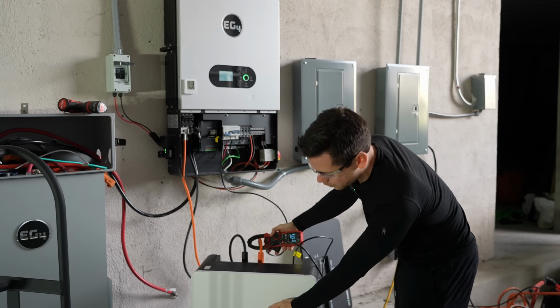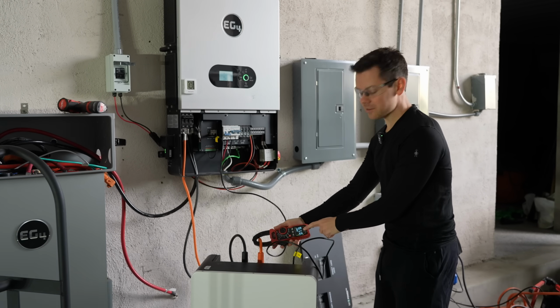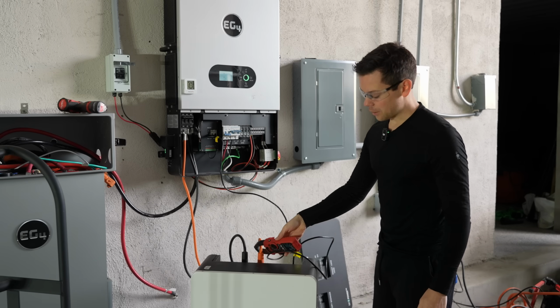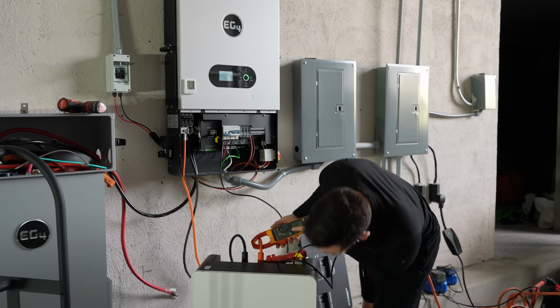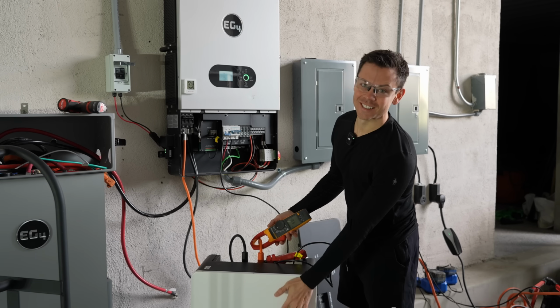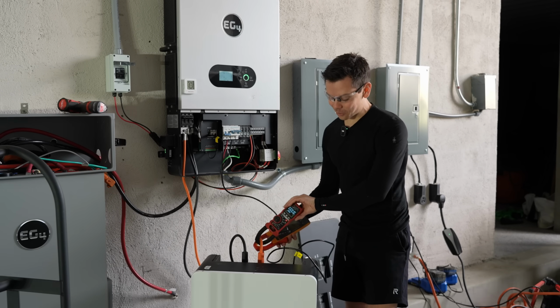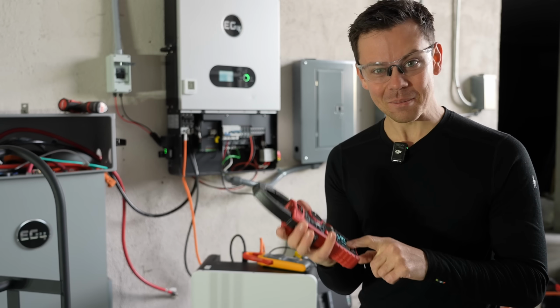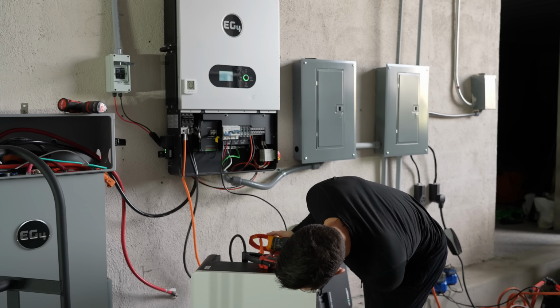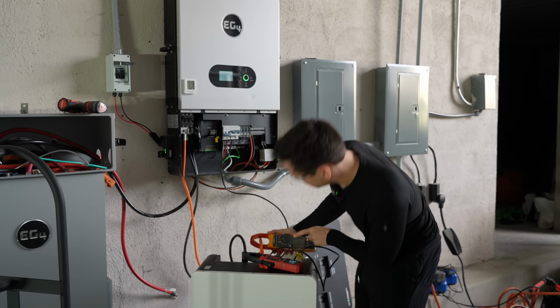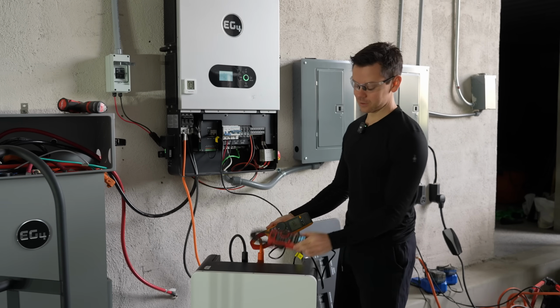It shows 64 amps on the screen, but it shows 72 amps on my meter. Let me get another meter just in case. The Fluke agrees with the screen, so yeah, this other meter is wrong, and it's off by quite a bit. This one shows 64, and down here we've got 64, so we're believing the Fluke over this thing.